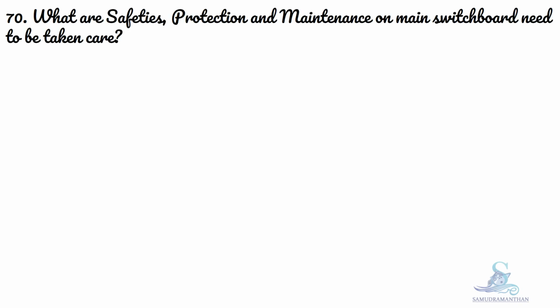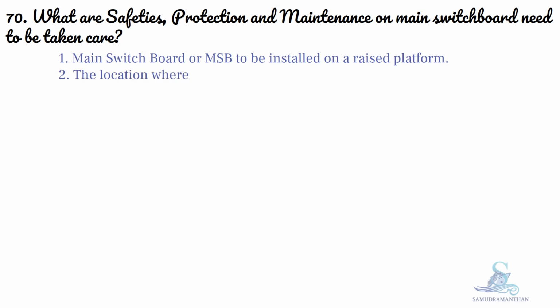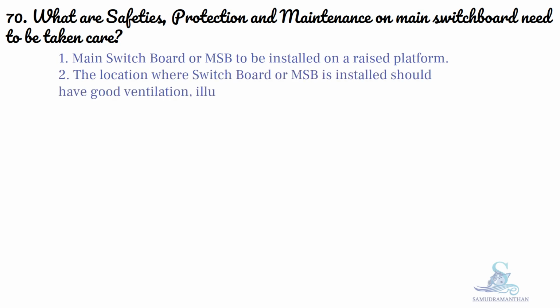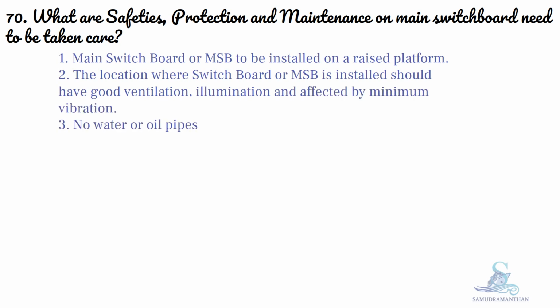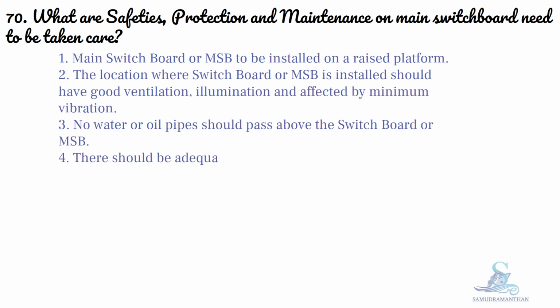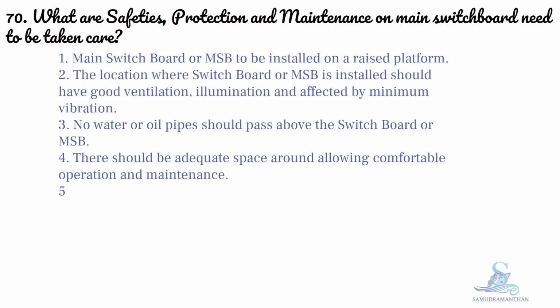What safeties, protection and maintenance on the main switchboard need to be taken care of? The main switchboard or MSB is to be installed on a raised platform. The location where the switchboard or MSB is installed should have good ventilation, illumination and be affected by minimum vibration. No water or oil pipes should pass above the switchboard or MSB. There should be adequate space around, allowing comfortable operation and maintenance.